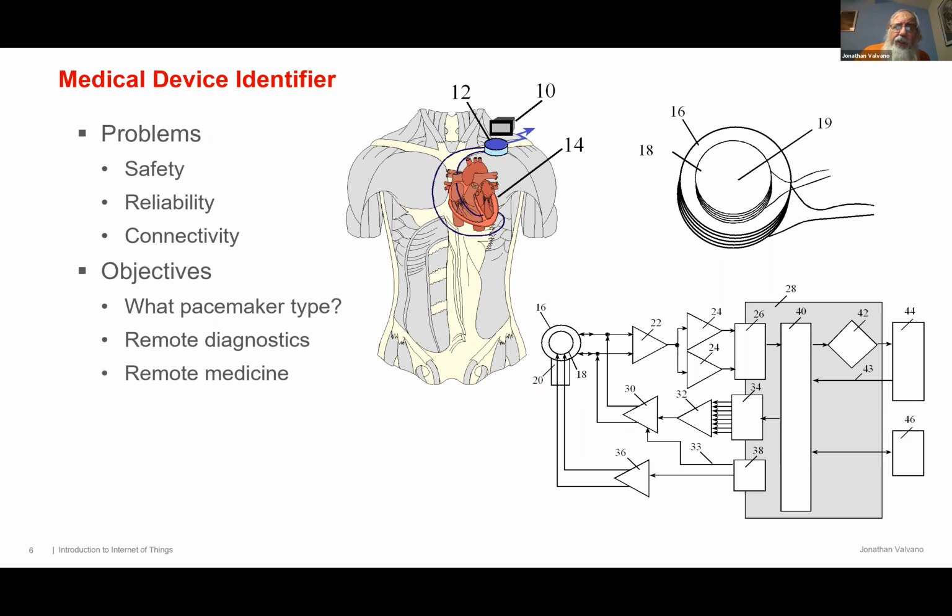The first communication is local and using a coil. There's a coil device that's passed over the patient. It doesn't have to pass energy because the pacemakers have their own batteries, but it does communicate with the device to say, hello, and then they respond, hola, and you know that's a Spanish one. Or if you go, hello, and they go, ciao, it's Portuguese, right? Each of the pacemakers has a certain protocol that they communicate with, and you speak the international language of hope, right? They start speaking in their own language, and you figure out who they are.